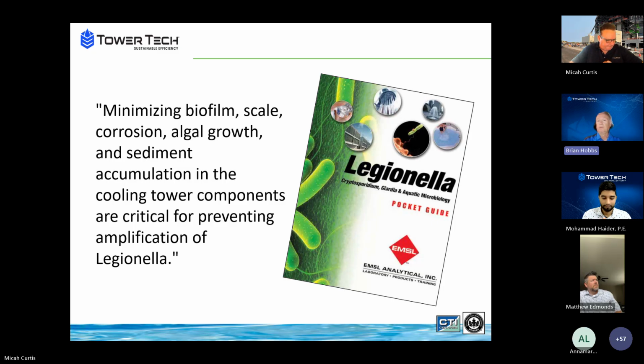Corrosion is one of the number ones, especially in dissimilar metal type cooling towers, and Mohammed will get more into that. And then in addition to that is all that sediment in those Legionella gardens that conventional cooling towers have in them, or all cooling towers of some types have. So the interesting part about this that is often not thought about is corrosion.